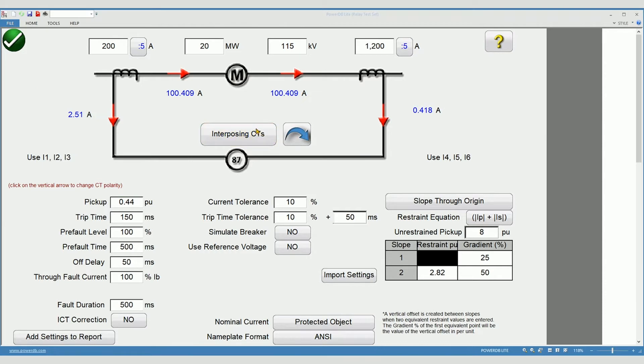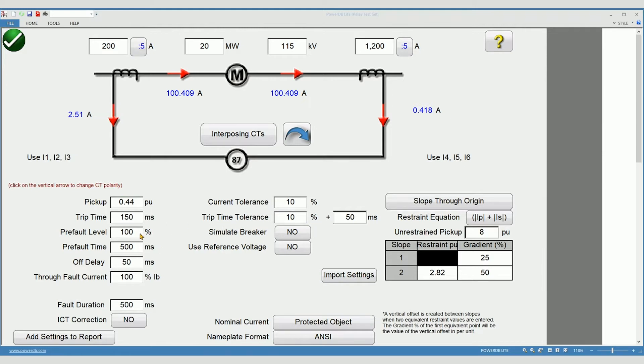Now we will move on to the relay settings. Enter the restrained pickup value in per unit, the allowable tolerance when testing, expected trip time and associated tolerance. The pre fault value to be applied before beginning the test and percent of full load.